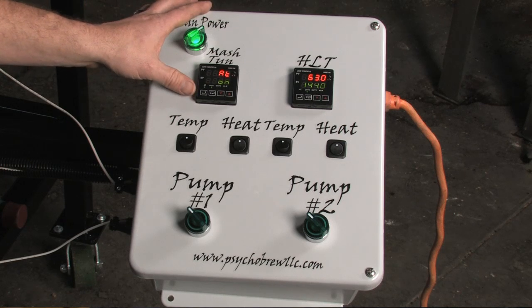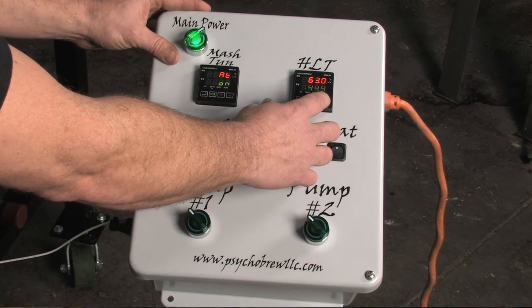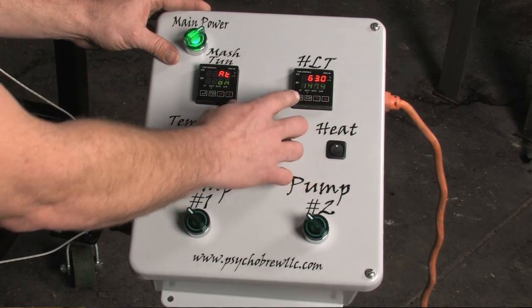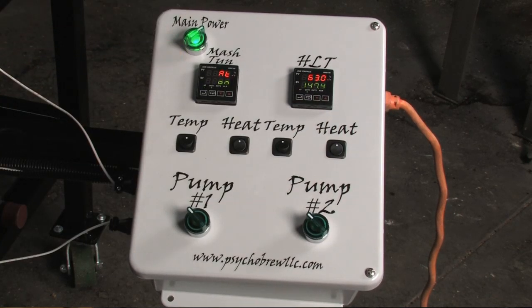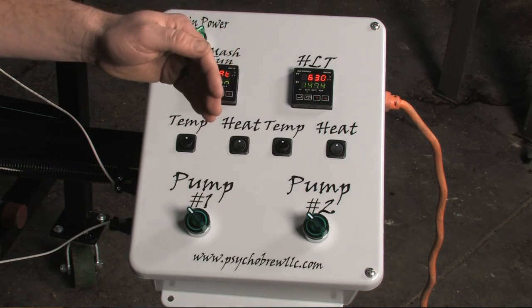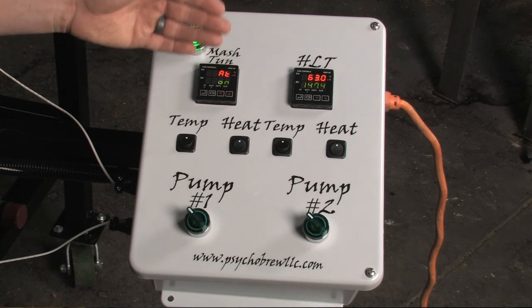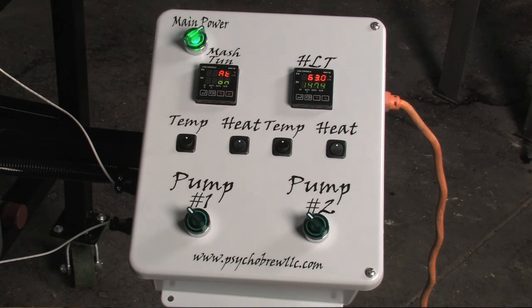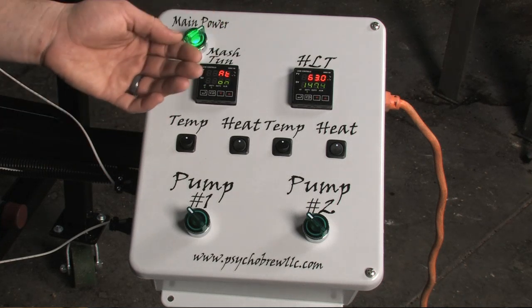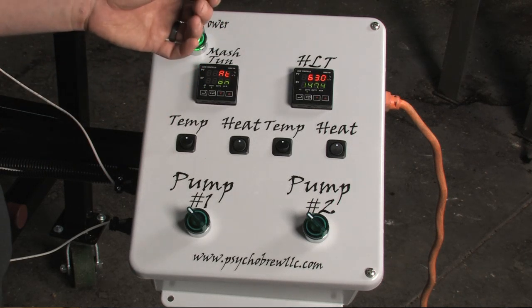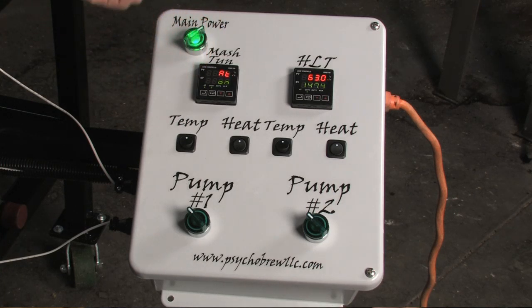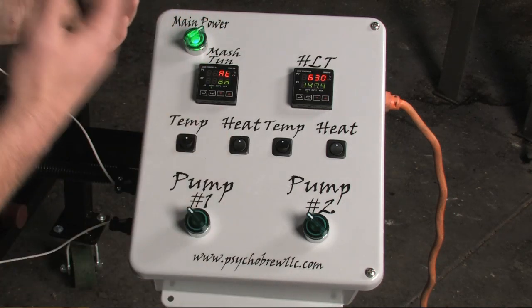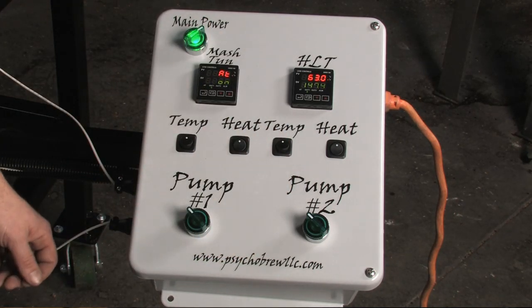If for some reason you desire a different temperature, simply hit the arrow button up on the temperature displayed and enter, and that's the temperature it'll try and control to. The logic inside the controller will learn the characteristics of what you're doing, so that if tomorrow you come back and turn it back on, it will replicate the same procedure you did today. And if you change that temperature, you have to go back in and turn auto tune back on, and then it will learn that temperature also. So you can flip between 2 or 3 or 4 different temperatures and it'll remember it all.